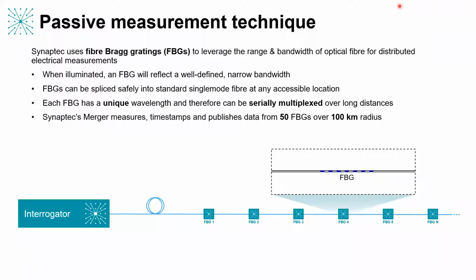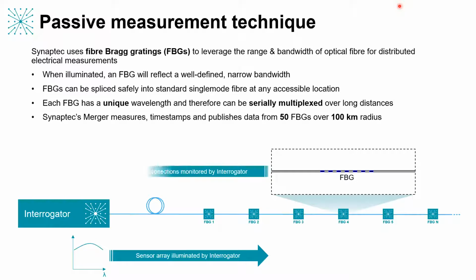So Synaptec developed an optical type of sensor that utilizes a very common type of fiber optic sensor called a fiber Bragg grating. Now, a fiber Bragg grating is an optical sensor for strain and temperature fundamentally. And the way that it works is, if we send broadband light, which is light of a whole wide range of frequencies, down the optical fiber, each of our sensors, each fiber Bragg grating, reflects back a very well-defined, tightly defined wavelength of light. Now that wavelength allows us to work backwards and find out what was the input that caused that. So if we vary strain or temperature, then the reflected wavelength from our FBG will shift up and down in terms of color.